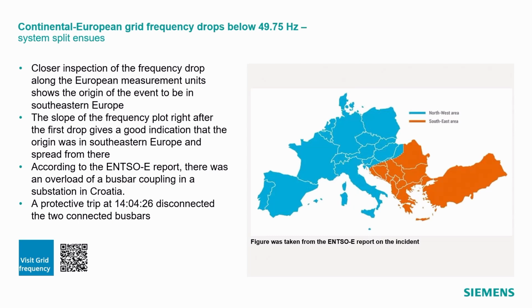A closer inspection was done by the European utilities, and this event was measured in different countries, starting from Eastern Europe to Dresden, Berlin, Vienna, France, and so on. And it was identified from the slope of the frequency plot that the problems happened in southeast of Europe. According to the report, see the link on the slide, there was an overload of a busbar coupling in a substation in Croatia. A protection trip at 2 p.m. 4 minutes and 26 seconds disconnected the two connected busbars, and the power grid came back to the level of 50 Hertz. Here you see in orange which part of Europe was disconnected from the blue part of Europe.